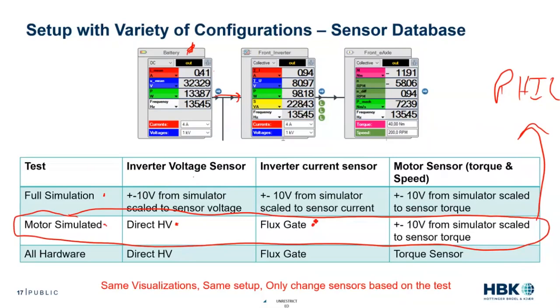We still want to understand how those inverter signals affect the motor. So we can measure the plus or minus 10 volt simulated scaled output of the OP45 and bring that in, looking at the theoretical efficiency of our modeled motor - how it reacts to this actual inverter. We start to see this really cool ability to understand inverter efficiency, but also potentially look at how that motor responds, getting an output and seeing its potential efficiency using those comparable equations. This gets me really excited because it's a way we can start to do tests on the benchtop without using valuable dyno time, without always needing a real motor. This is kind of bridging that gap.